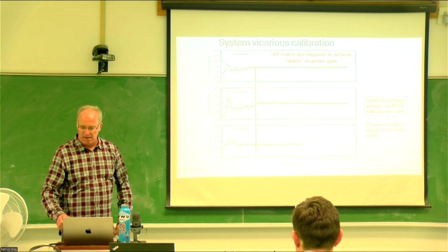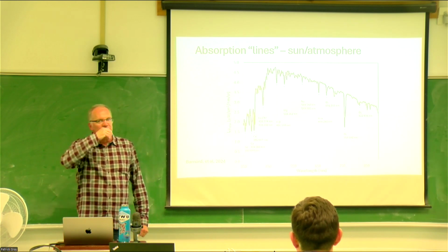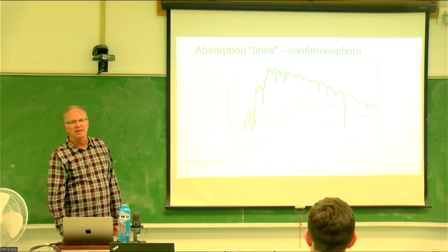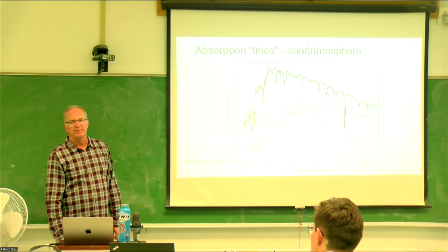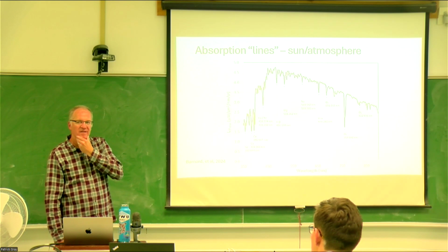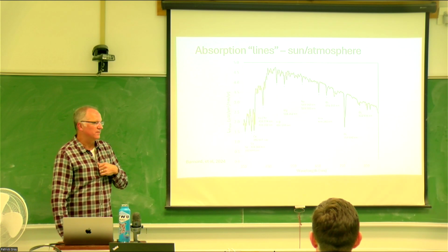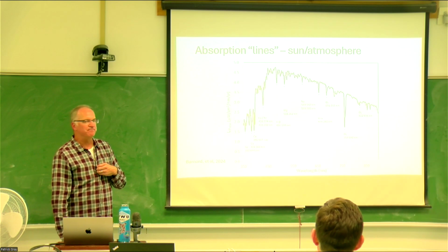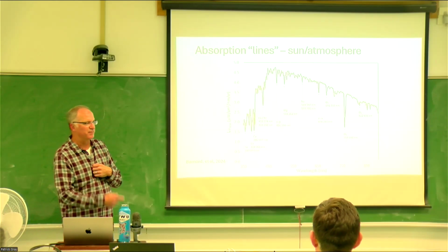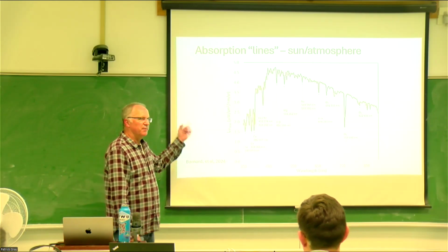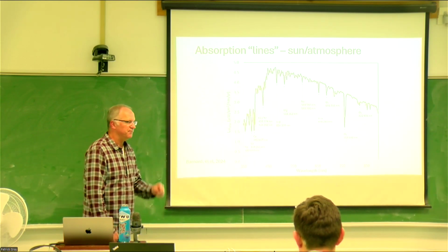This is from the HyperNav, right? Yeah, this is from the HyperNav. Andrew's machine. Think about the HyperPro and the PySAS and even the HSRD. You guys got that sun spectrum. And look at this, can you see the difference in spectral resolution? You have much more detail with this new system, which is super helpful. I'll get to more of a description of the HyperNav, but spoiler alert, the HyperNav measures at 0.4 nanometer spacing.